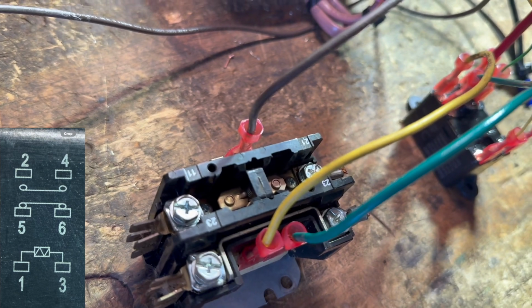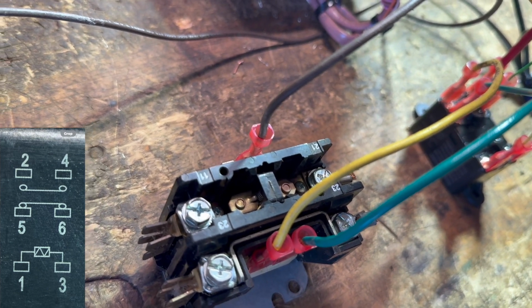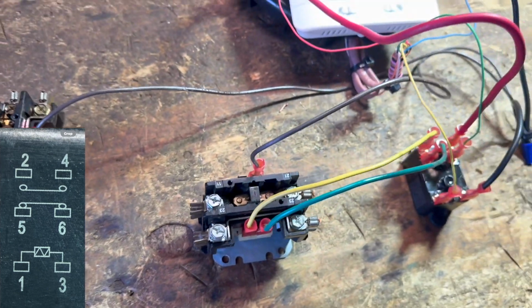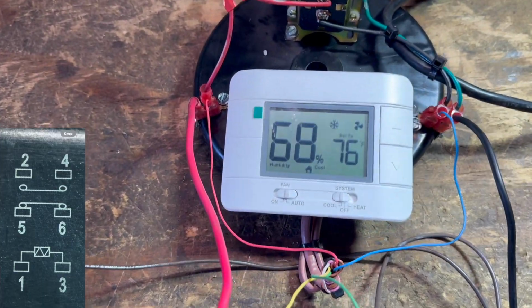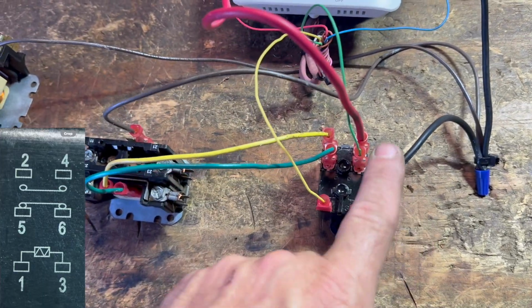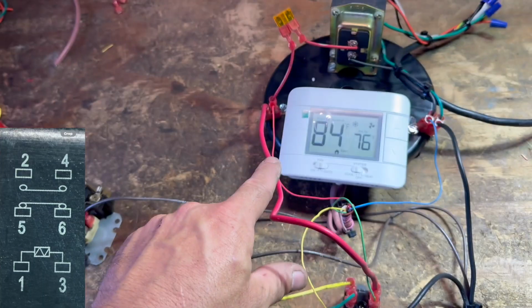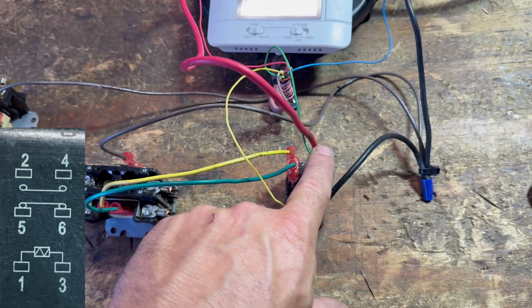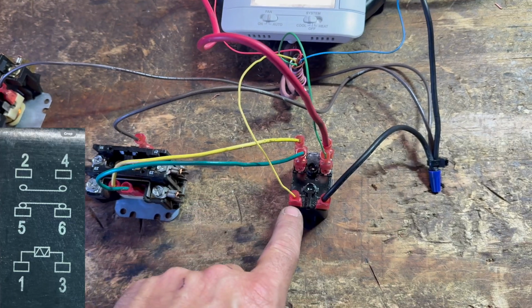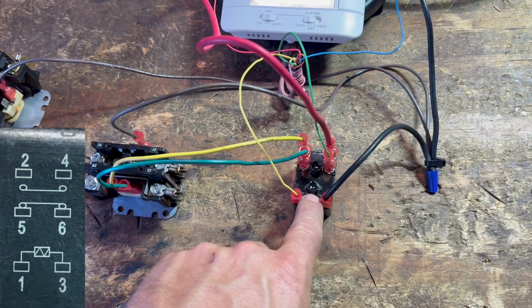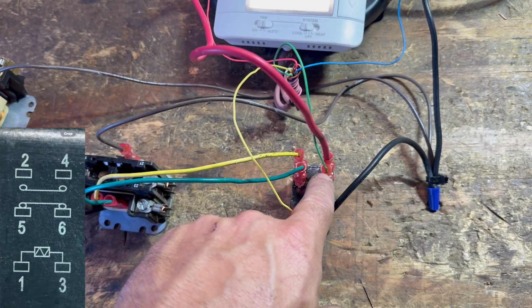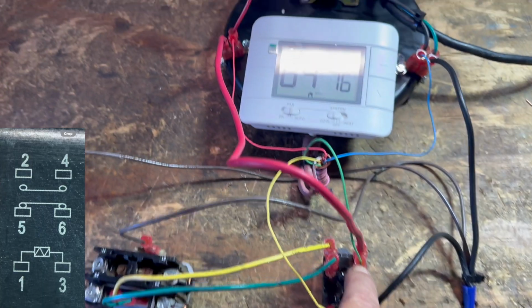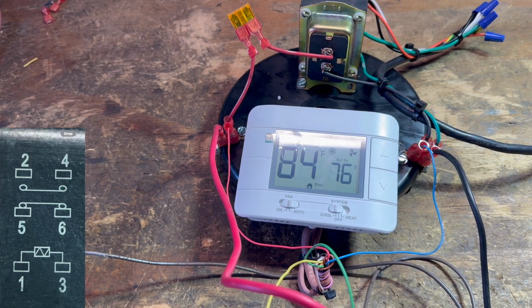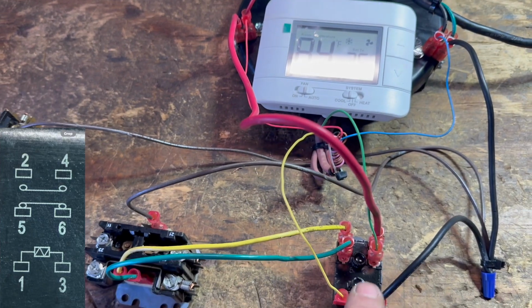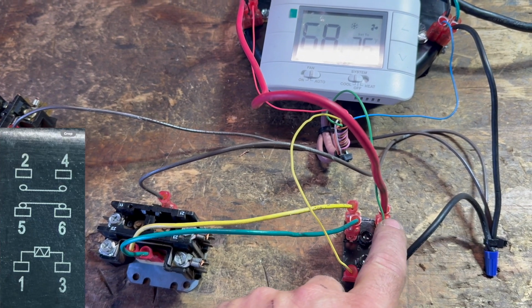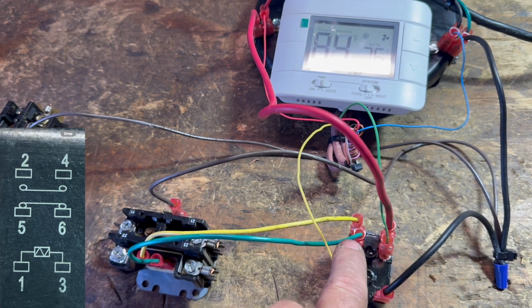There it is. Okay, now right now there is 24 volts actually going to both of these. So I have a constant 24 volts on this red, which is then connected to the yellow once this load is activated. But there's also 24 volts from green, because when the thermostat tells the outdoor unit to come on and throws that yellow signal, it knows it needs to operate the indoor fan, so it's going to put 24 volts on that green as well.